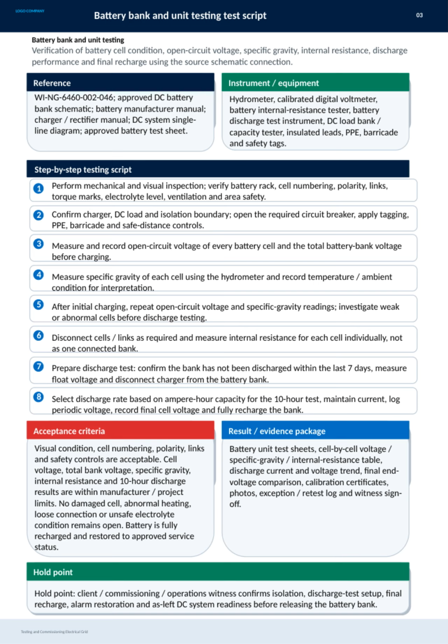Preparing for the discharge test requires confirming that the bank hasn't been recently discharged, measuring float voltage, and disconnecting the charger. The discharge test itself is conducted using an ampere-hour-based rate over 10 hours, maintaining current and logging voltage periodically to evaluate performance. The battery bank is then fully recharged. The acceptance criteria require all visual and electrical parameters to fall within manufacturer and project limits, with no damaged cells, abnormal heating, or unsafe conditions. Finally, comprehensive documentation, including test sheets, calibration certificates, photos, and logs, serve as the test evidence. This whole process concludes with a hold point where client and operational teams witness and confirm the battery bank's readiness before it returns to service.